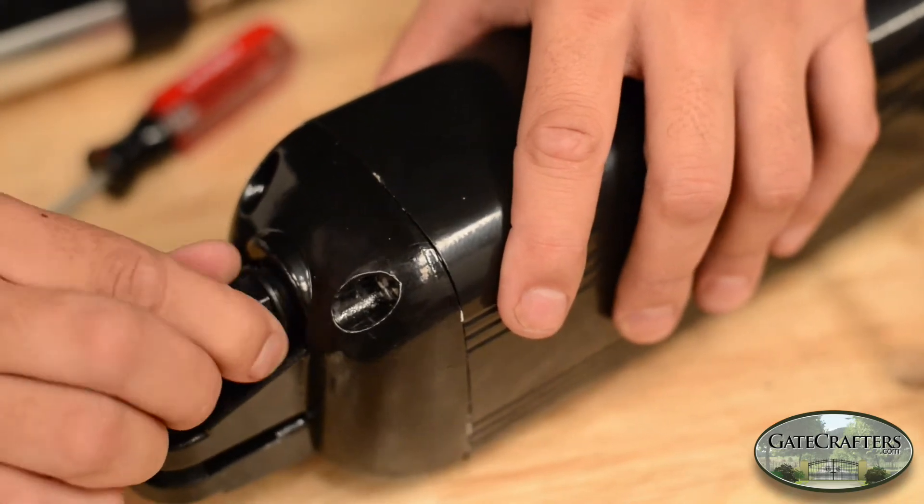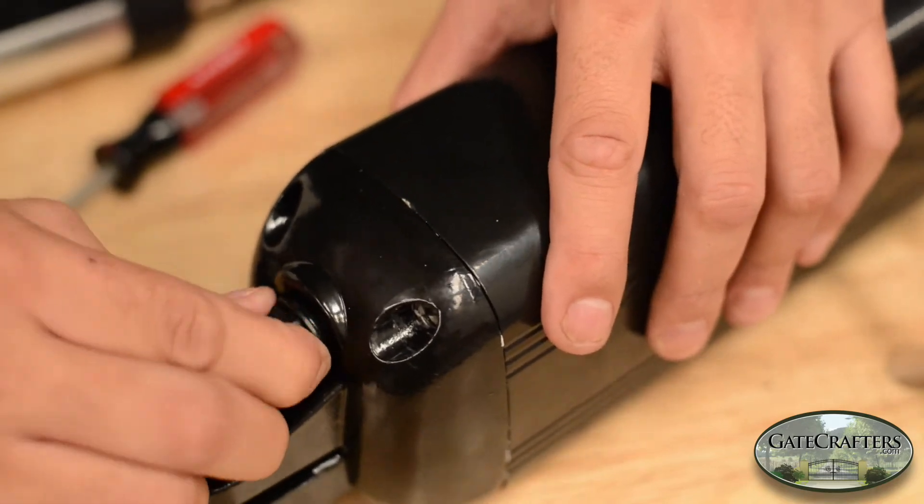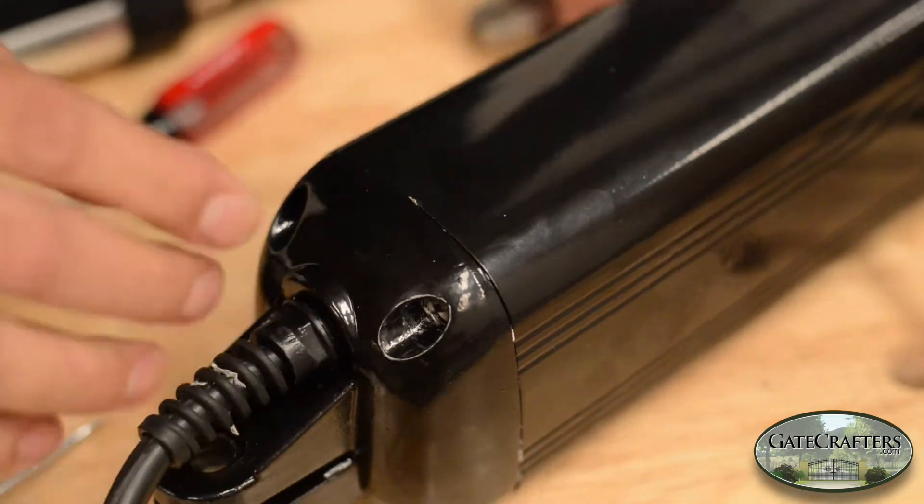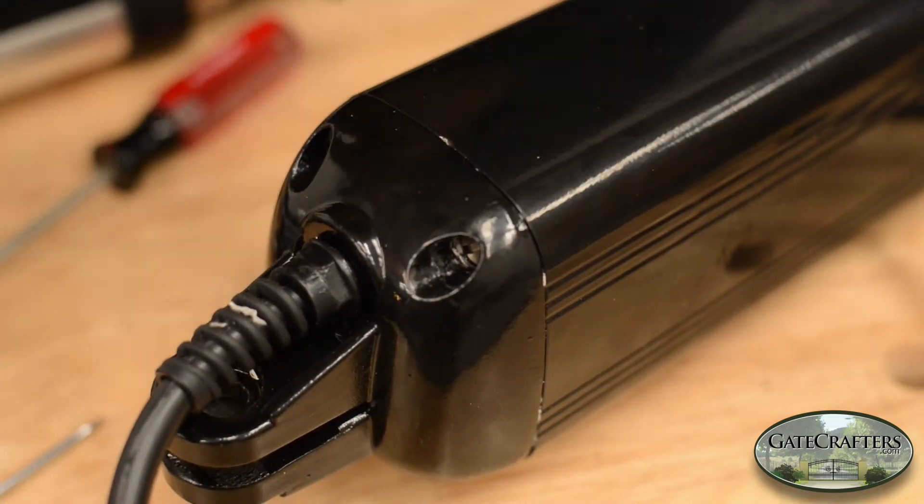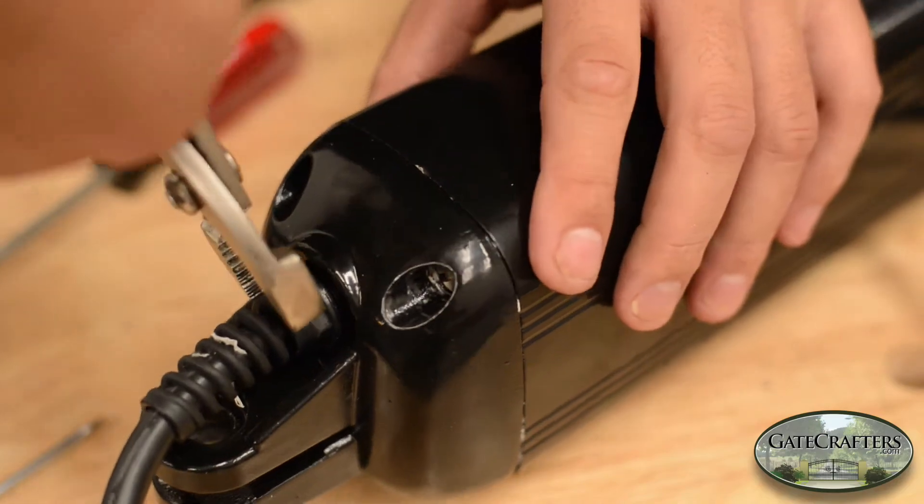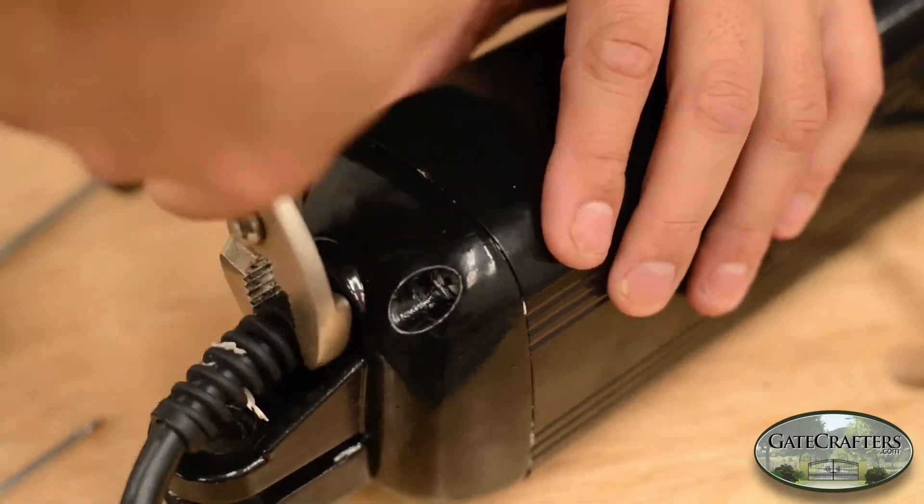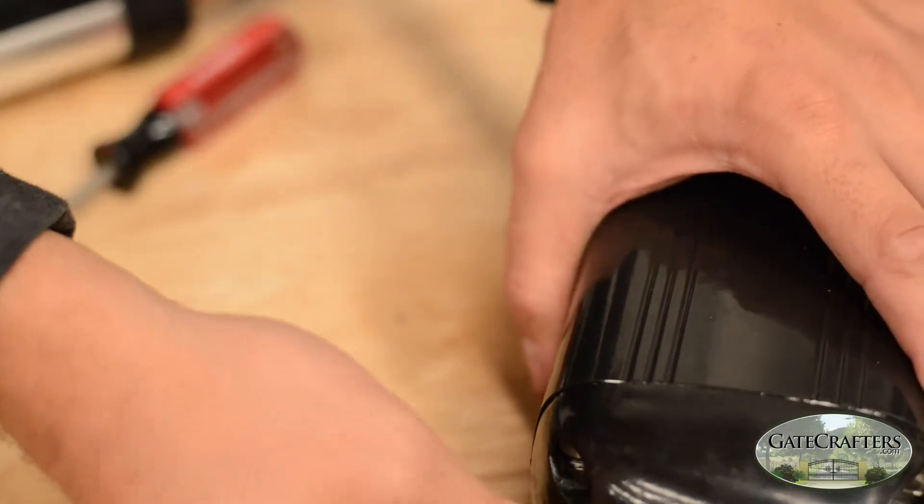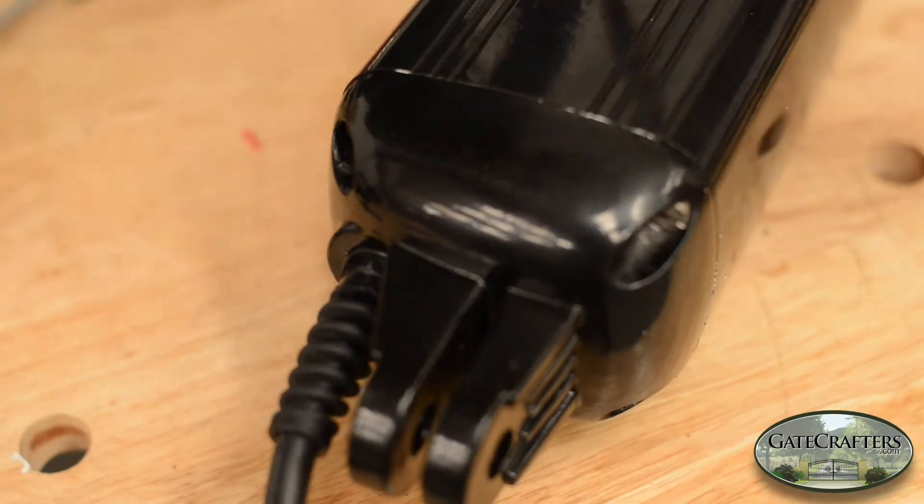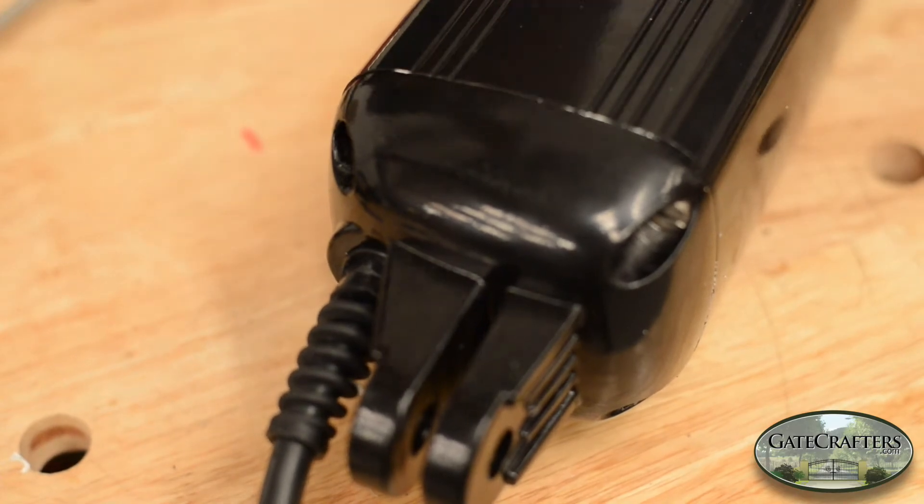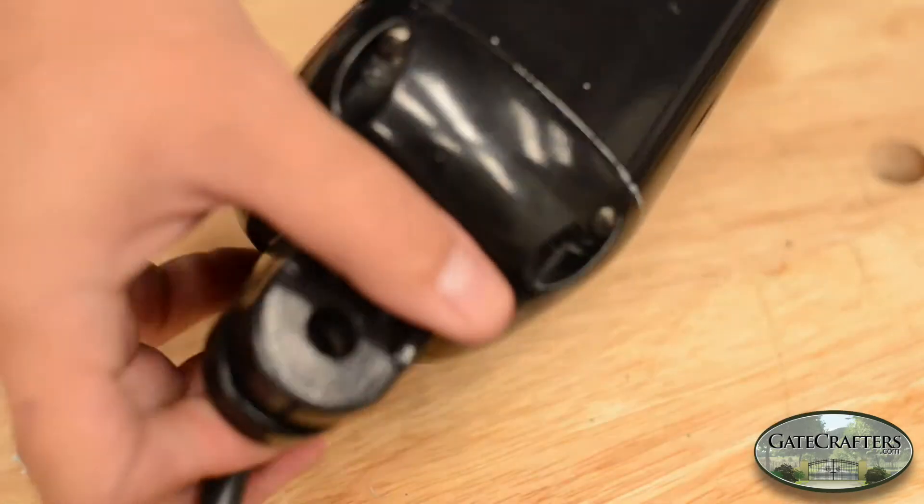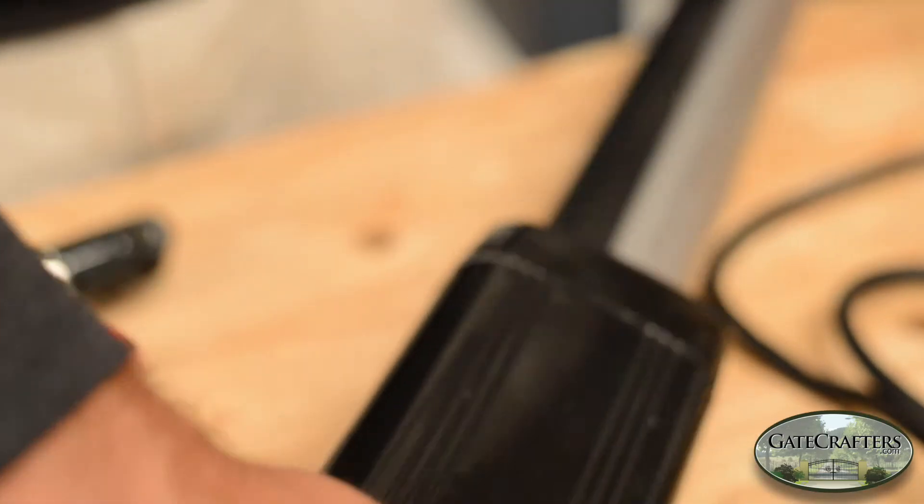It'll go the majority of the way with your hand, and then you can use the pliers to get all the way tightened down. That's nice and tight. And one more test to make sure nothing fell off while we're putting that back together. We'll check the continuity one more time and test the limit switches one more time. Make sure that we're good to go.